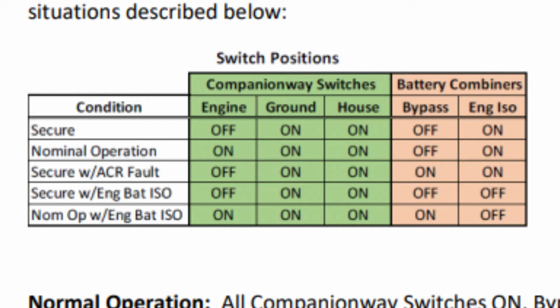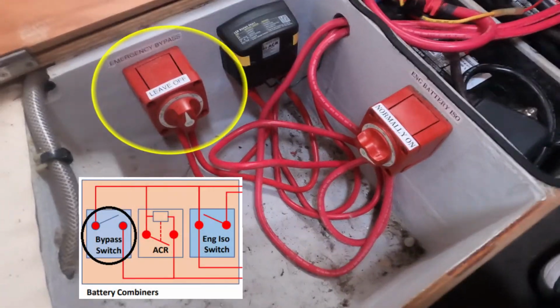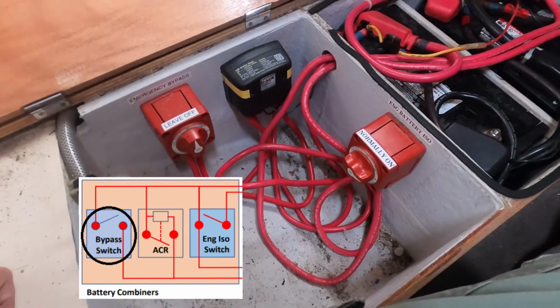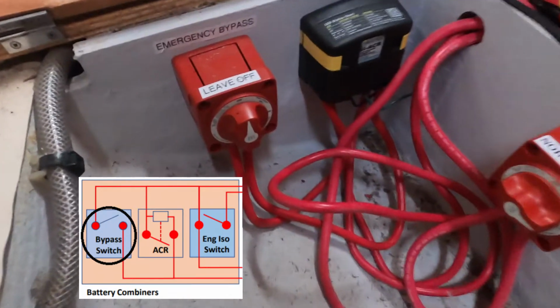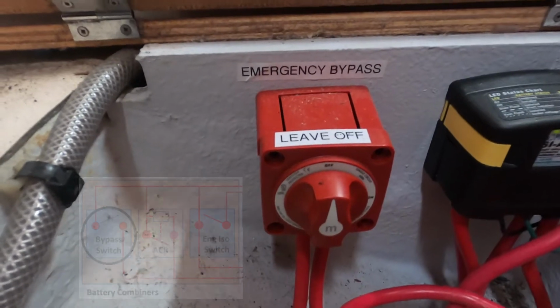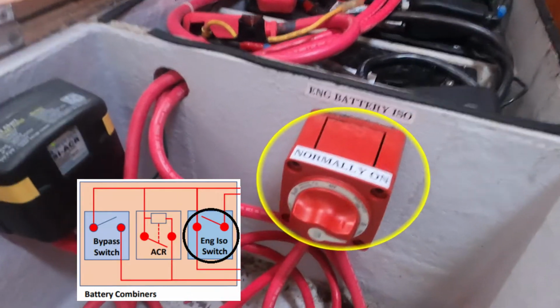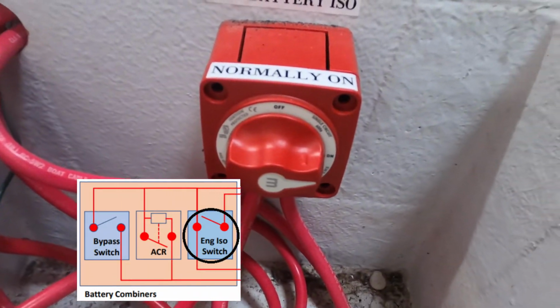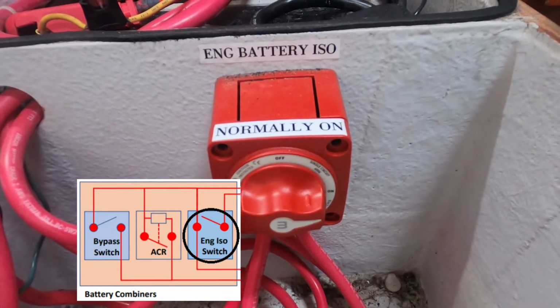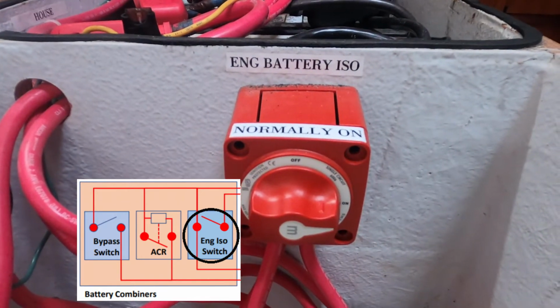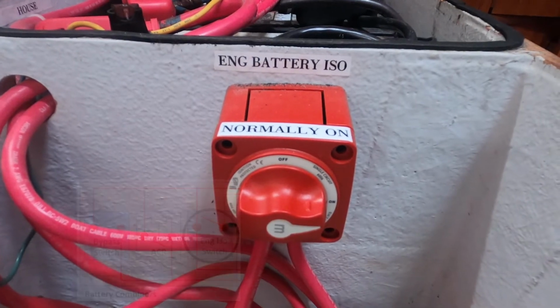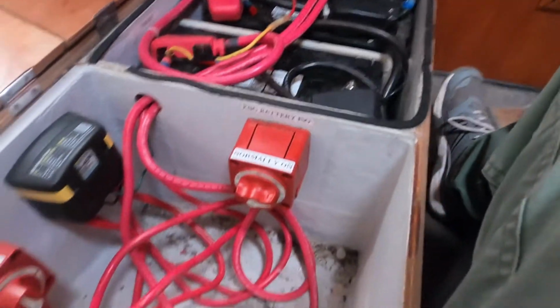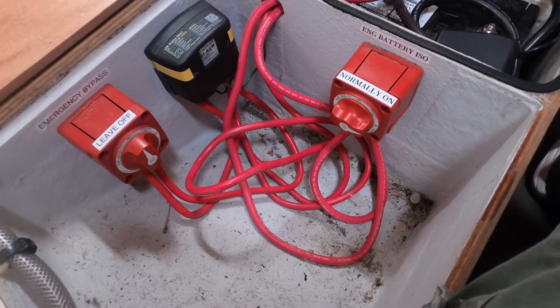So you have all these different conditions. If we go back to those switches, you'll see they are labeled. The emergency bypass, which bypasses that ACR, is said to be left off unless it's needed. The other one is the isolation switch, where you'd disconnect the engine battery, and that's normally on. But if you had a fault in the engine battery, you'd want to turn that off. So it's complicated, but if you follow the diagrams and the table, it tells you what you need to do.